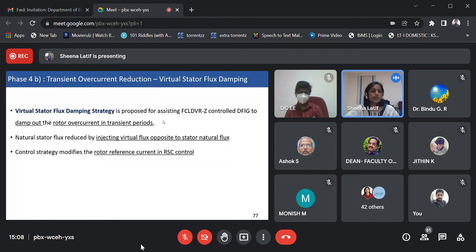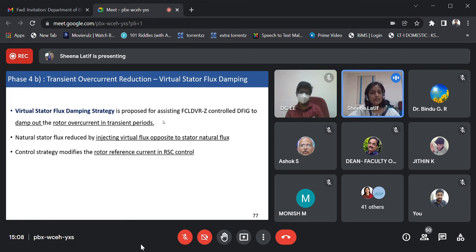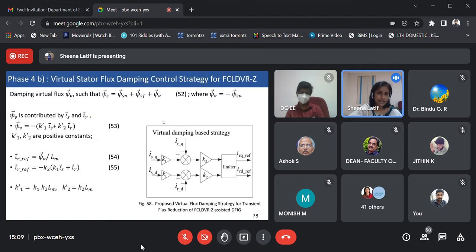So the steady state overcurrent is well reduced by the FCL DVR impedance method, but there is a slight rise in the rotor current in the fault clearance period, which has to be reduced, and we are proposing to reduce it using a virtual stator flux damping strategy. In the virtual stator flux damping strategy, the natural component of the stator flux is opposed with the virtual component, and thus the stator flux natural component is reduced. And this is applied to the rotor reference current in the RSC control.